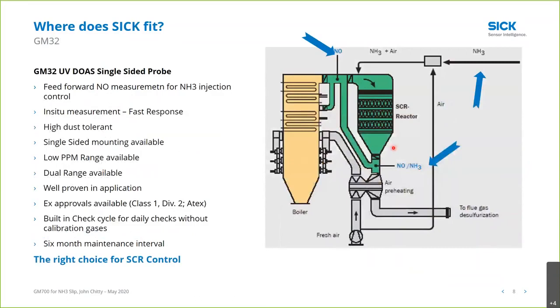So in an SCR, we have a catalyst bed. It is a reactor, basically. The flue gas comes in, and when the flue gas comes in, we have an opportunity here to measure NO. This is a different measurement from ammonia slip, and we use the GM32 in situ analyzer to measure NO here, and this gives us a feed-forward signal to the ammonia control system. And on the outlet of the SCR, we have another opportunity here to measure NO to calculate the efficiency of the SCR, and this is where we would measure ammonia slip as well.